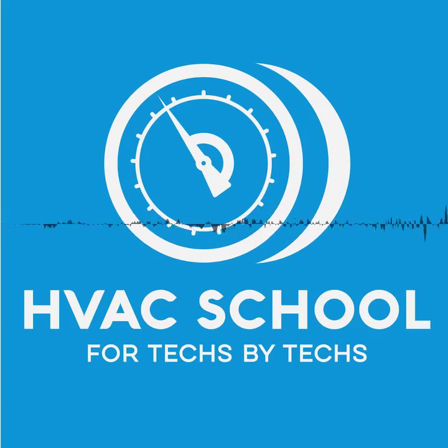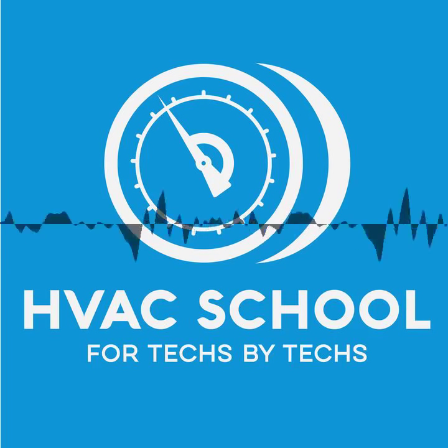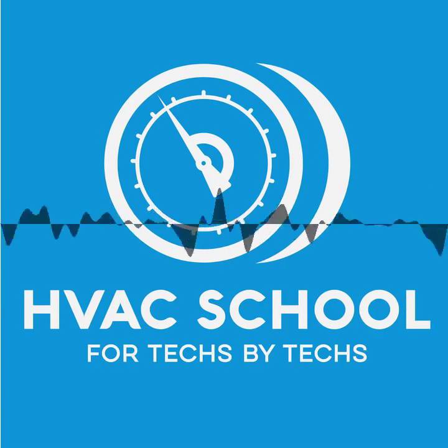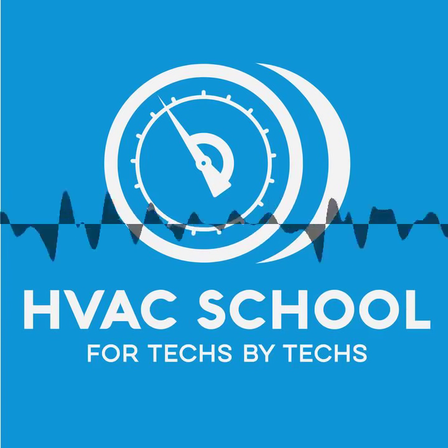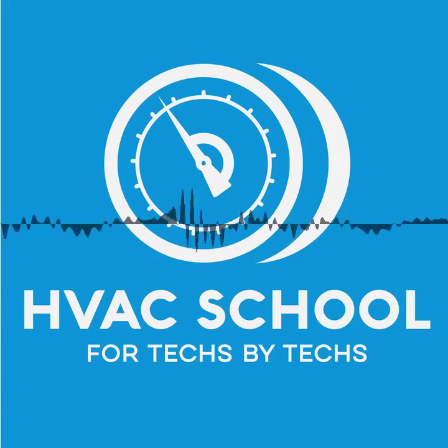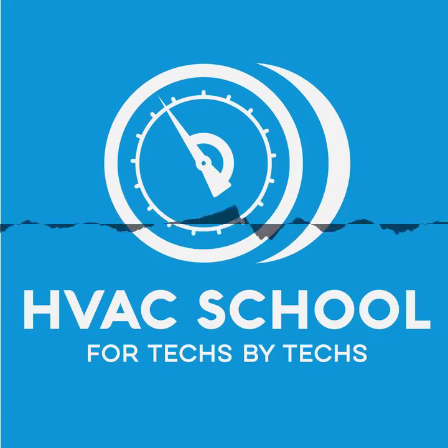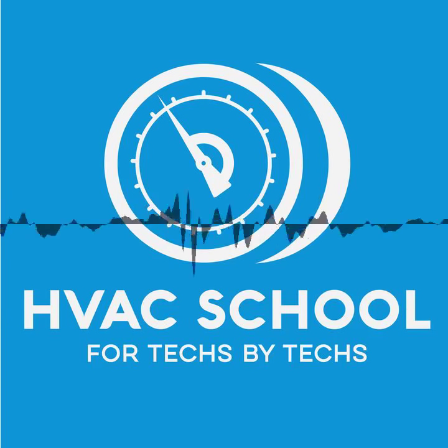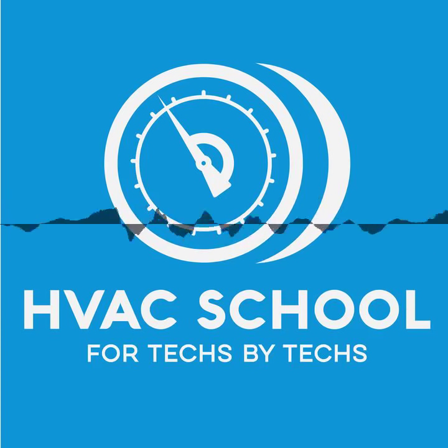Thank you. So let's get into these controls here. Let's start with just talking about temperature controls and how they differ from HVAC controls, or AC controls, I should say, air conditioning thermostats. What are some things that can make them different? Well, I would say the biggest thing is just the temperatures at which we're controlling. When you're looking at a standard air conditioner, what are you looking at? Like 45 degree evaporator temperature, 55 degree evap temp? Is that about accurate? Yeah, anywhere from a 35 degree evaporator temperature at the very coldest up to maybe 55 if you're under really high load or something like that.